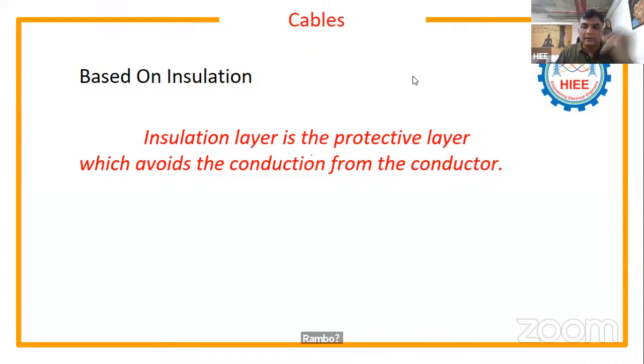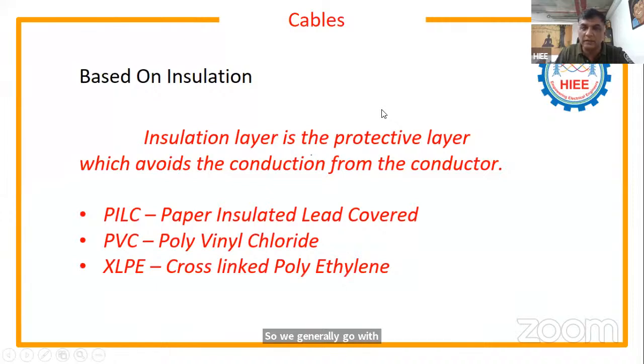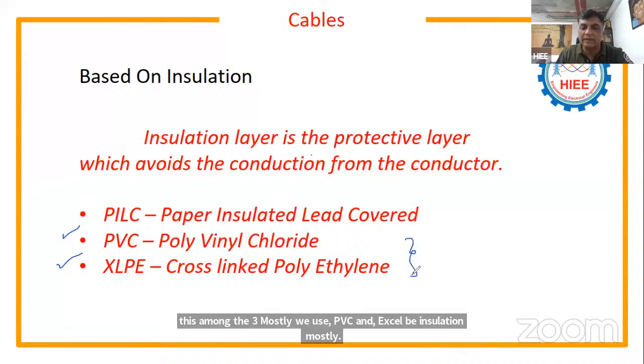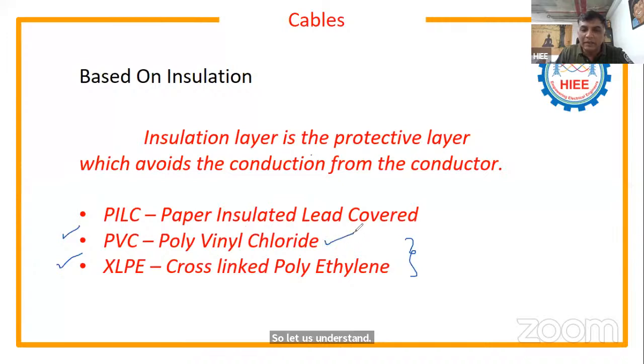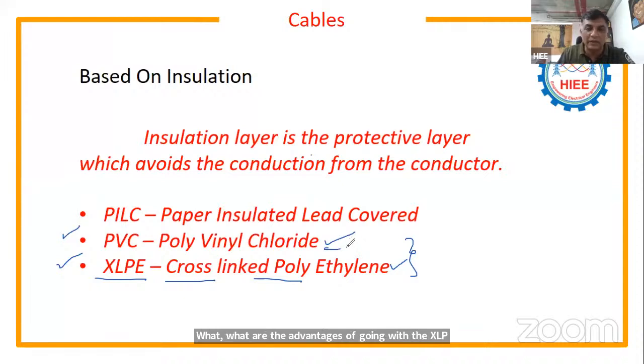Yes, thank you. So insulation is the protective layer which prevents conduction from the conductor. We go with different insulation materials above the conductor. Generally we use three types of insulation: paper insulated lead covered, polyvinyl chloride, and XLPE insulation. Among the three, we mostly use PVC and XLPE insulation. So let us understand where we use PVC insulation, where we use XLPE, and what the advantages of going with XLPE insulation over PVC are.